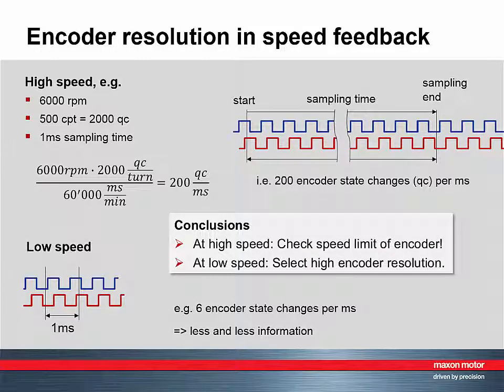There are two conclusions. First, at high or very high speed, verify that the encoder supports the high mechanical speed and that the encoder and controller can handle the high encoder signal frequency.